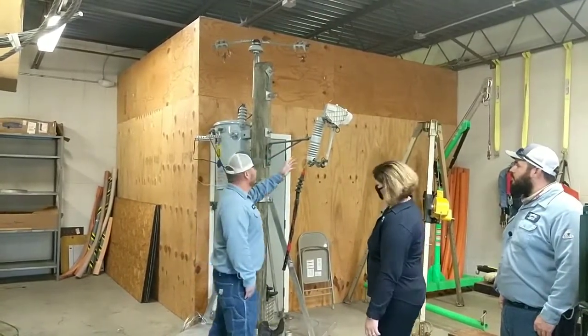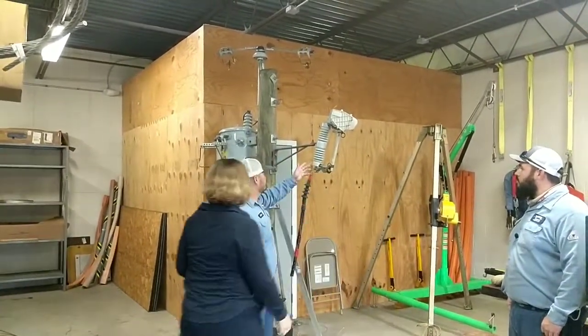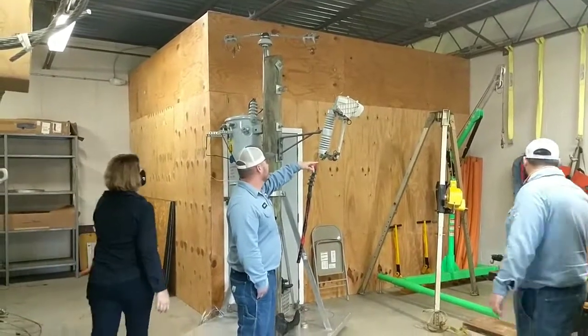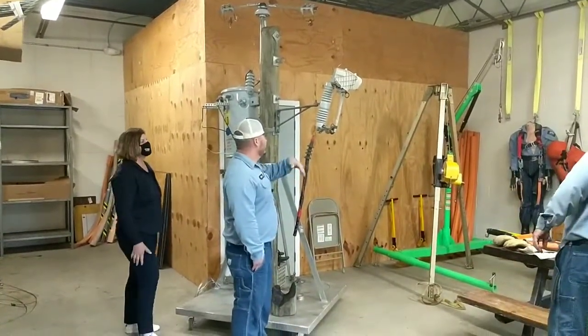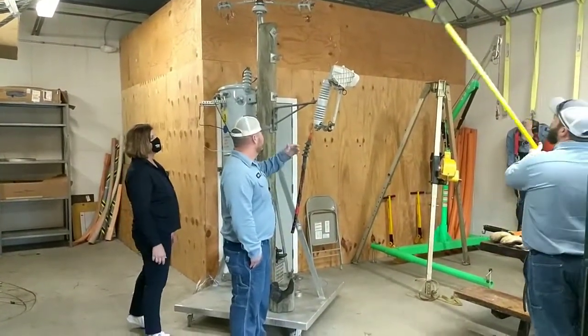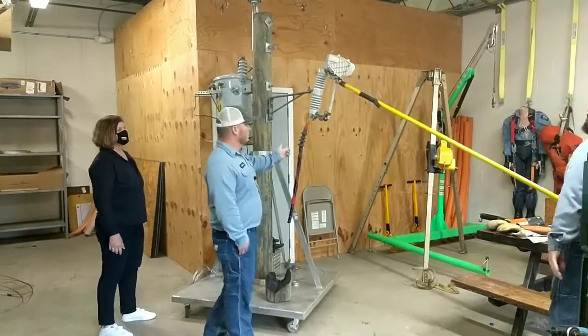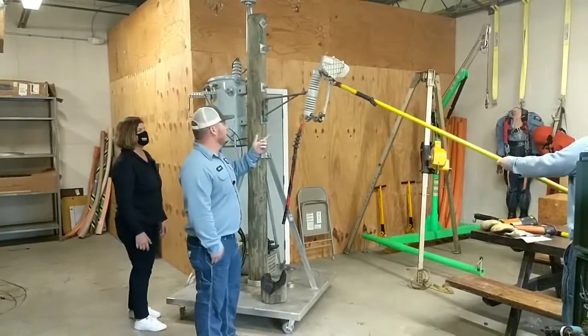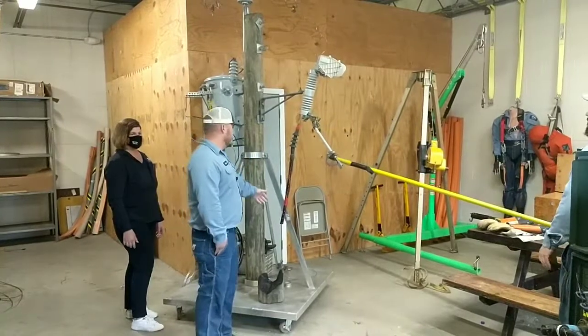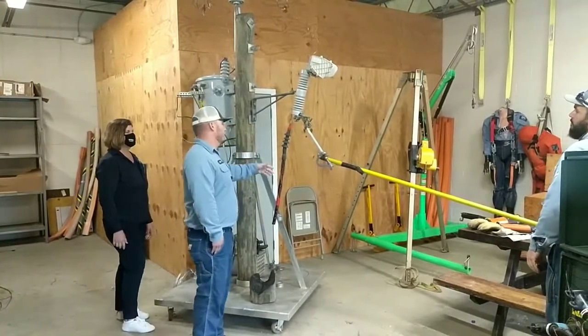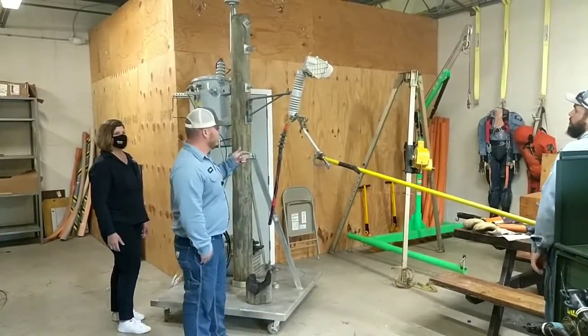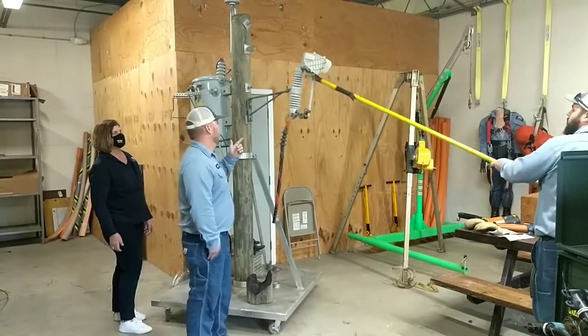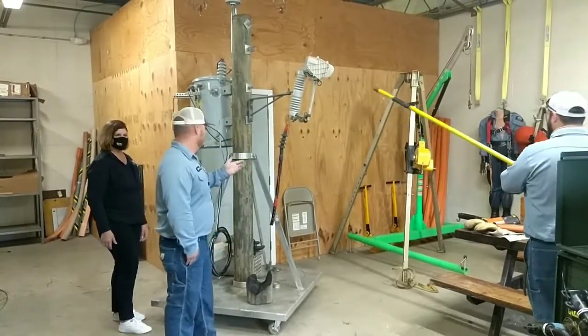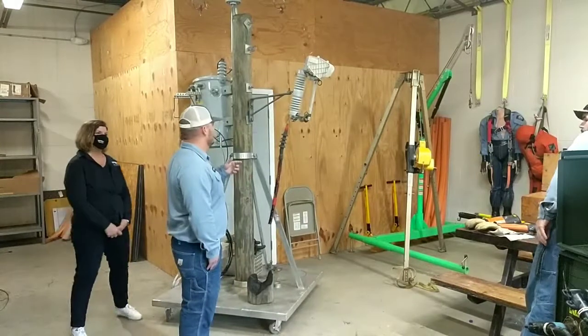This device here is actually the switch and has the barrel inside of it. When you operate this barrel, it pretty much kills the power to any kind of tap or underground. He's going to pull this jack and that'll de-energize this bottom side, the cable, the underground. And when we're ready to re-energize it, he'll throw it right back in. It's as simple as that, to de-energize and re-energize the line.